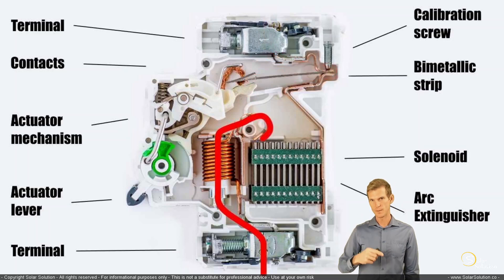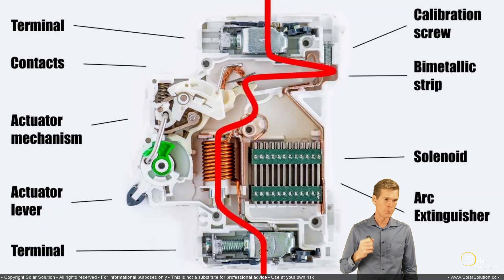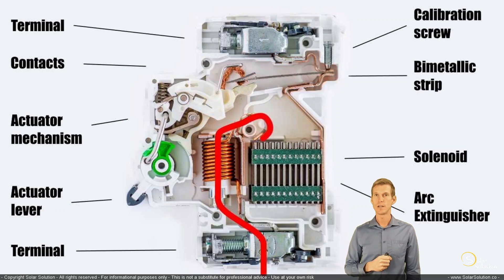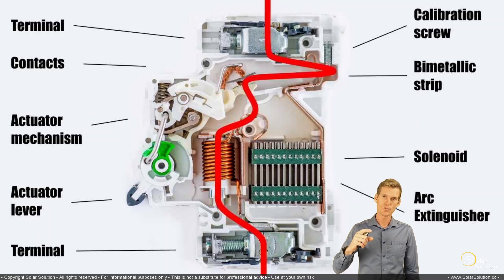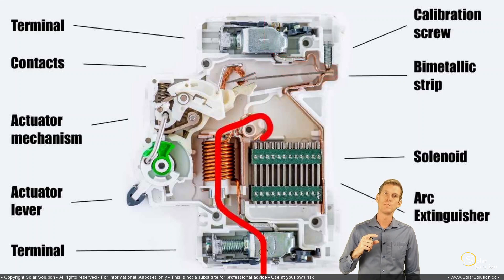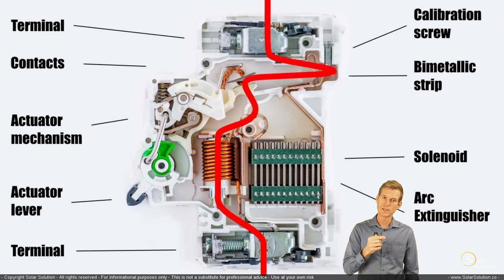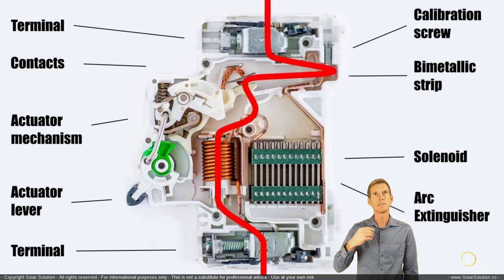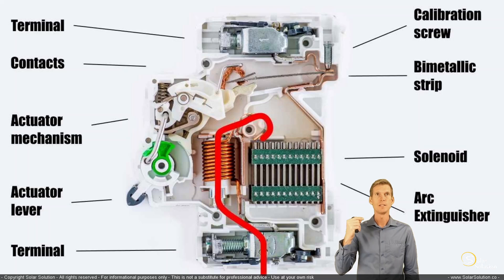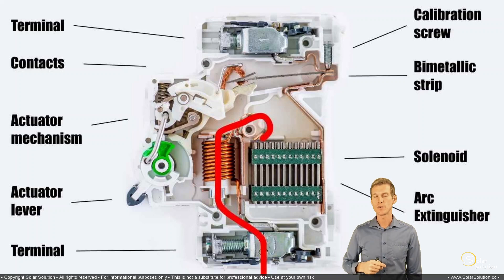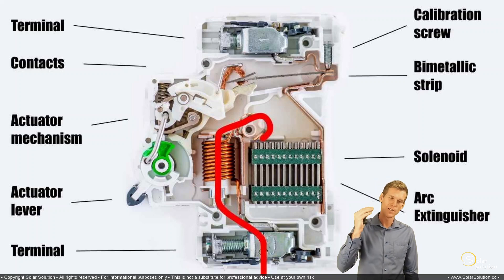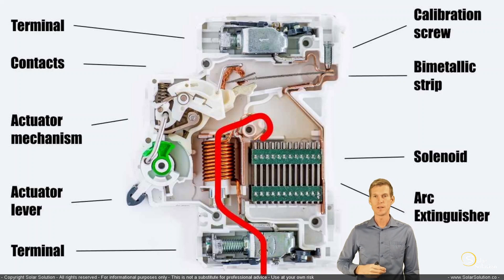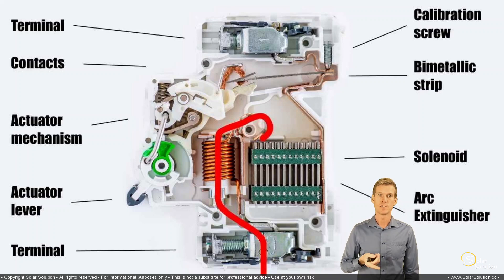Similarly for the instantaneous tripping current — all current runs through both the solenoid and the bimetallic strip. But if there's a sudden extreme increase of current, the coil inside the solenoid activates, pushes the mechanism, trips it, and the contacts open. So the circuit can be interrupted in three ways: the bimetallic strip bending from the slow tripping current, the solenoid activating from an instant burst of high current, or manually flipping the actuator lever.